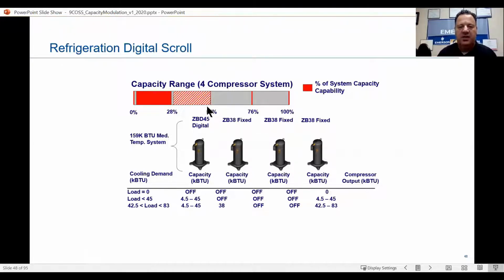So now we're running at 10 seconds on, 10 seconds off. And when I say on and off, excuse me, I'm used to saying on and off, but it's loaded or unloaded. It's not shutting off. The digital is not shutting off. That's the sweet part of having a digital, okay? You're not turning that on and off and running that electric bill up, all right? Those contactors aren't getting pitted.